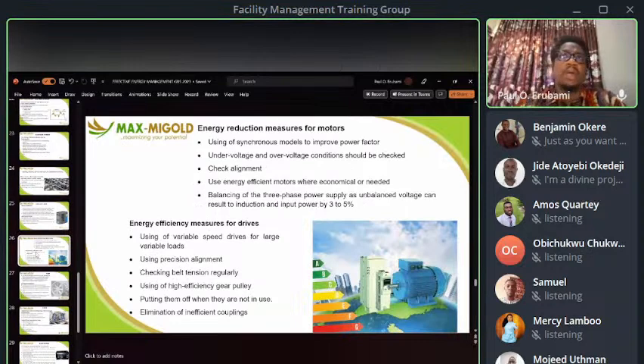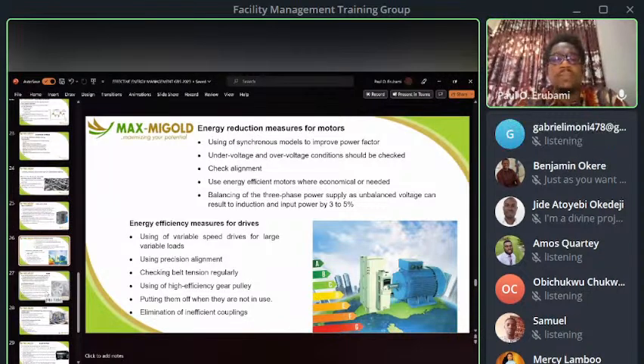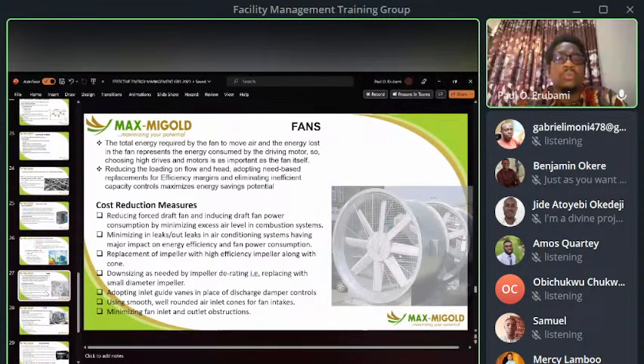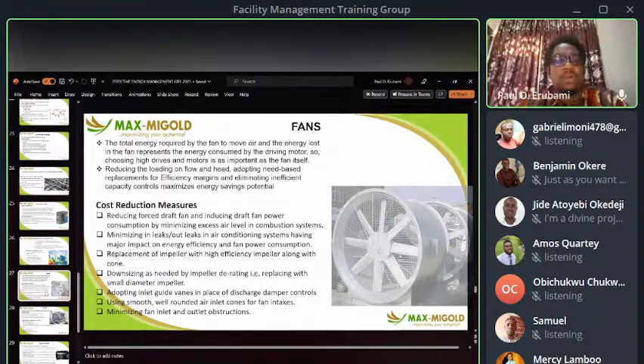A lot of industries need to pay attention to this, especially those manufacturing industries where energy cost is sometimes running more than 40-50% of your energy use. Think about how to implement motor controllers that can help the equipment to work evenly and respond to loads. For fans, reduce forced draft fan and induced draft fan power consumption by minimizing excess air level in combustion systems. Minimize leaks in and out of air conditioning systems. Replace impeller with high efficiency impeller along with cone. Downsize as needed by impeller, derating, and so on and so forth.